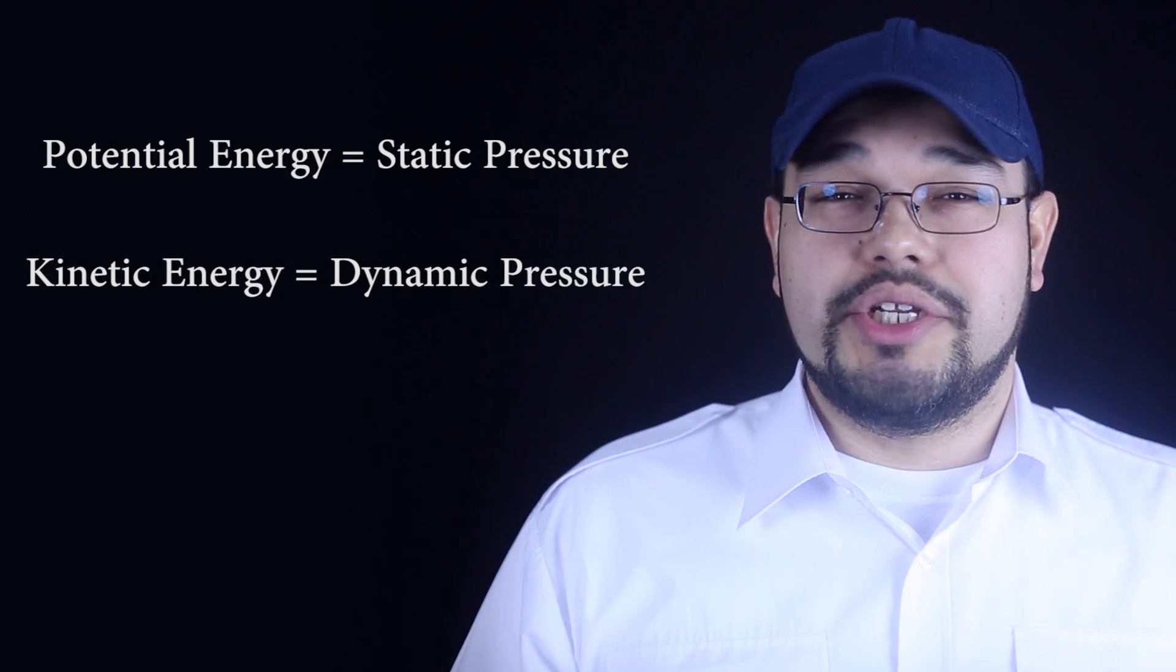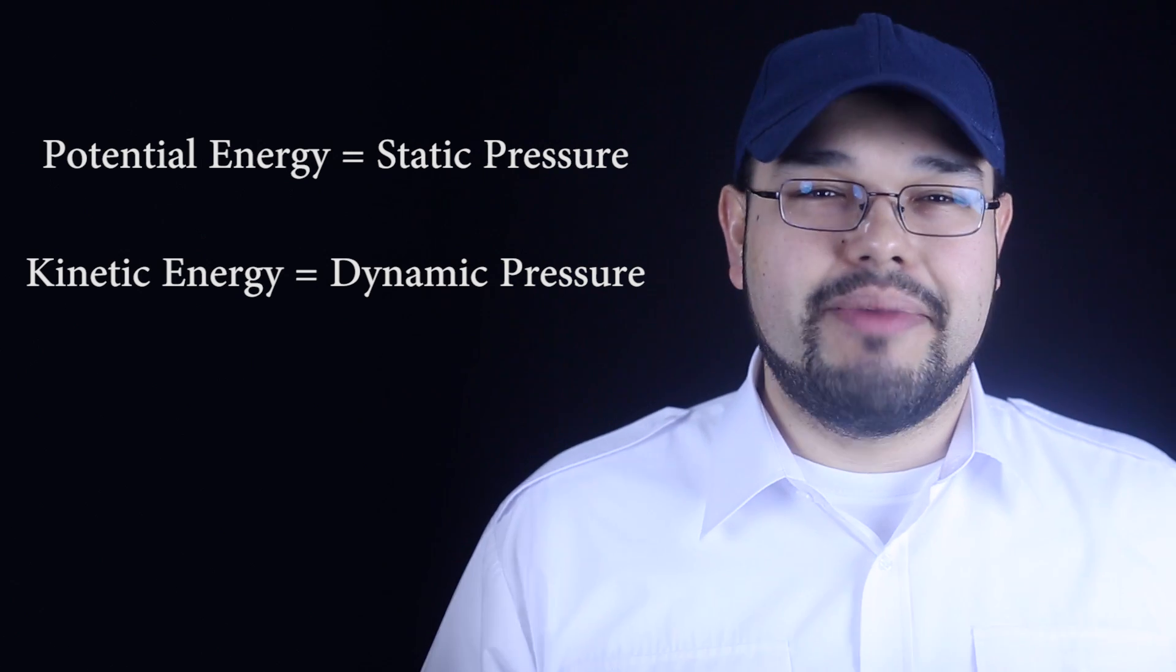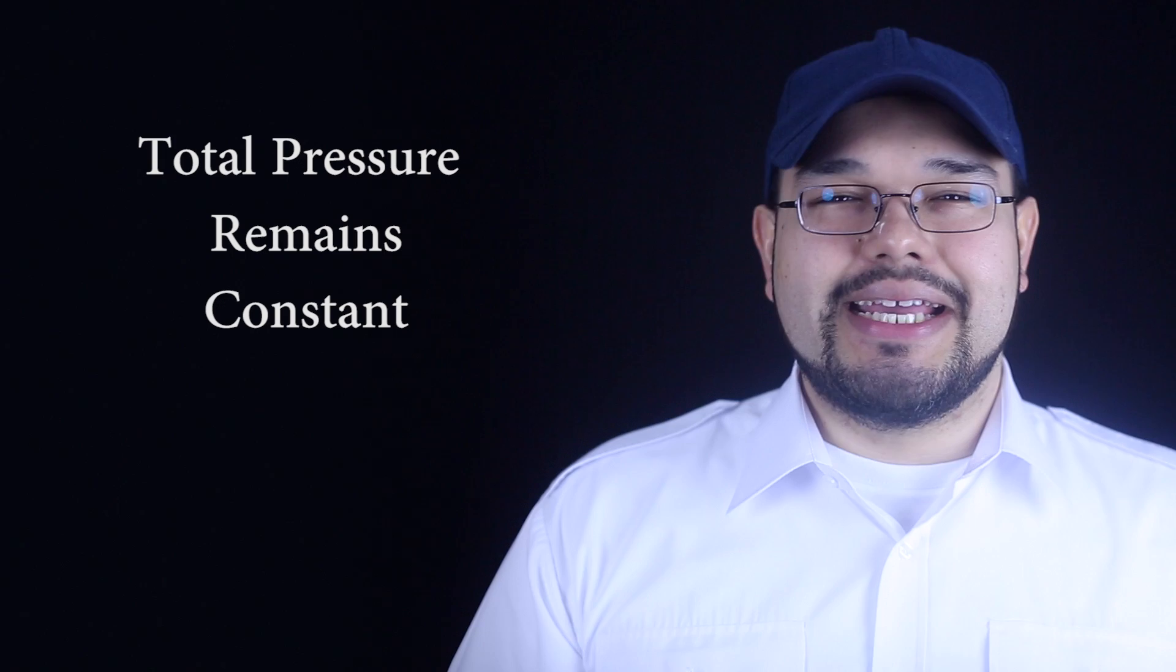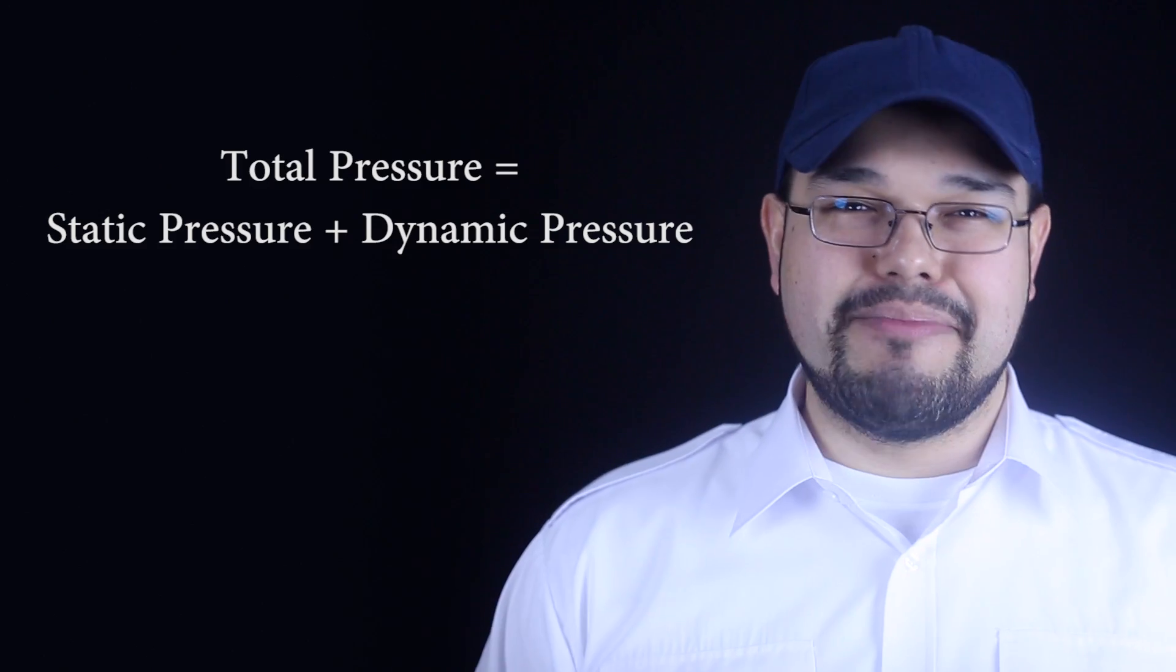So building upon this, Bernoulli's principle explains the behavior of pressures in gases. In an airstream, there are two forms of energy. Potential energy, which is the airstream's static pressure, and kinetic energy, which is the airstream's dynamic pressure. So Bernoulli's principle states that total pressure remains constant. Total pressure is made up of static and dynamic pressure. Represented mathematically, total pressure equals static pressure plus dynamic pressure.